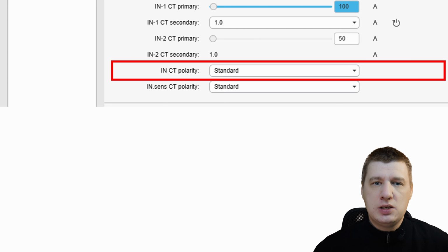In the P5, standard polarity usually refers to the default resistive mode. In this mode, the relay expects the fault current to be largely in phase with the residual voltage, as in common grounded networks. Physically, standard means your CT is installed with the P1 terminal facing the busbar and the secondary wires connected correctly to terminals A13 and A14. But not every network is the same.